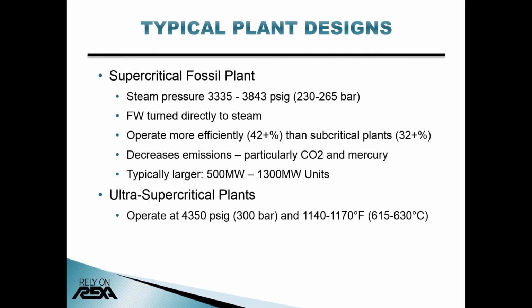Ultra supercritical boilers take these higher pressures and temperatures to a new level at more than 4,200 psi and 1140 degrees Fahrenheit. Their operation is practically identical to the supercritical design, with a bump in efficiency up to 55% and further reduced CO2, NOx, and SO2 emissions.